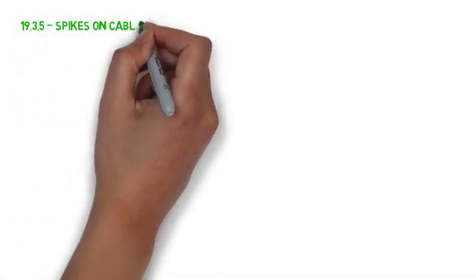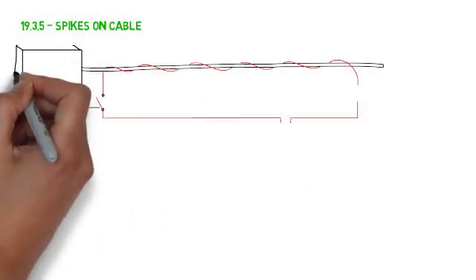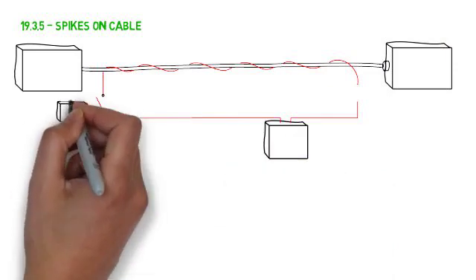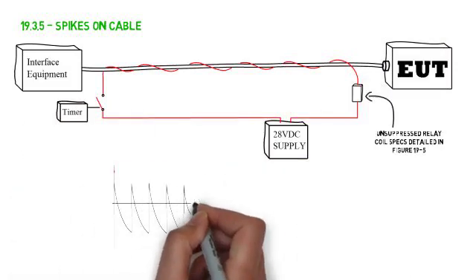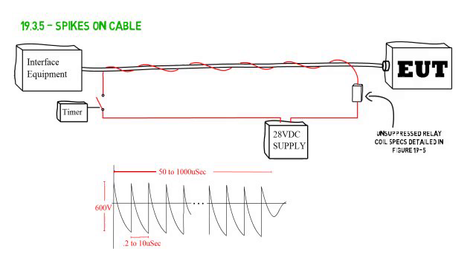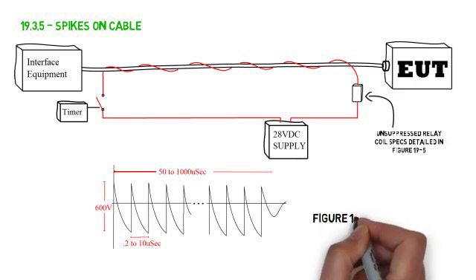Lastly, spikes induced on the interconnecting cable is run using the setup shown. The setup in DO-160 shows a 28-volt power supply. However, the only requirement is that the signal achieved complies with figure 19.6 of DO-160.